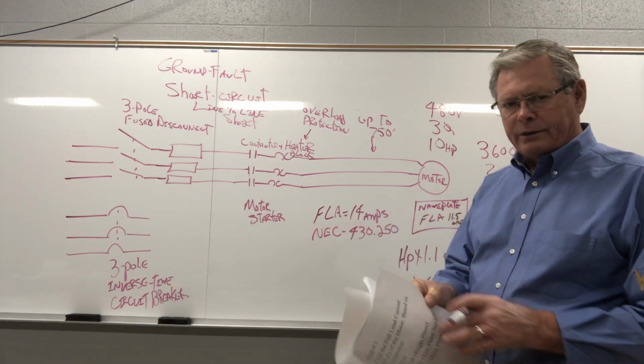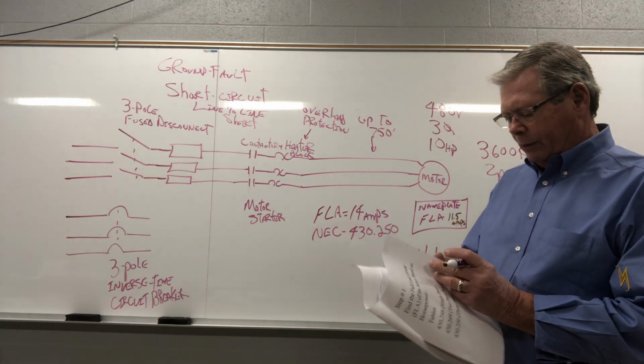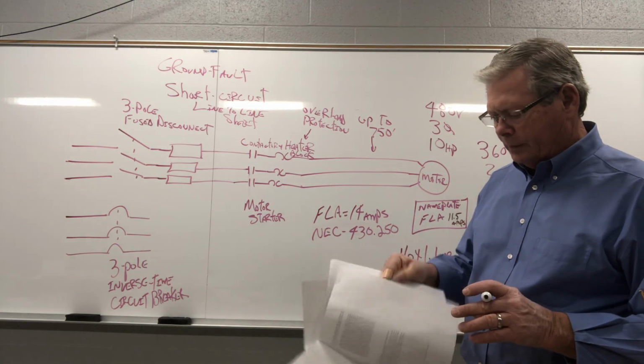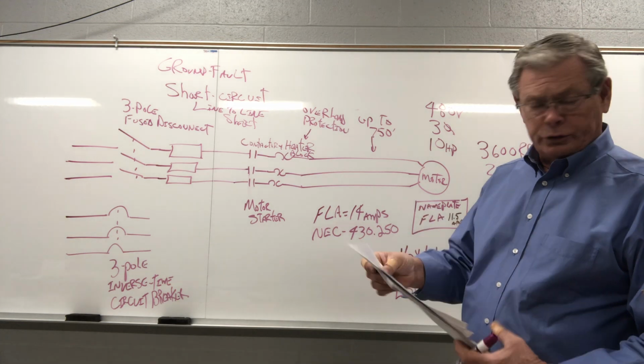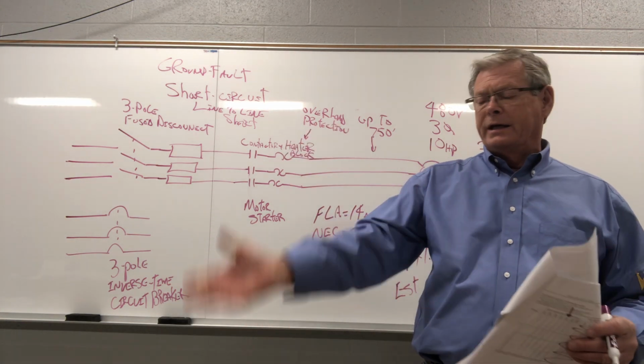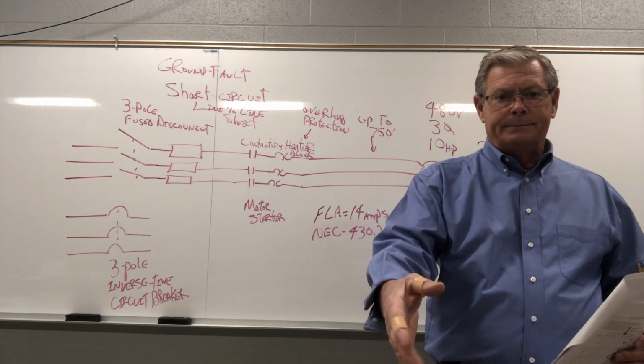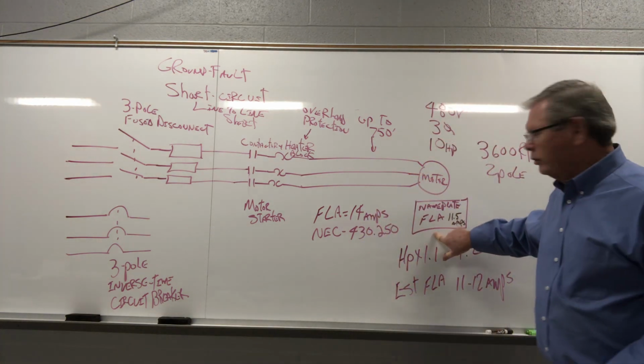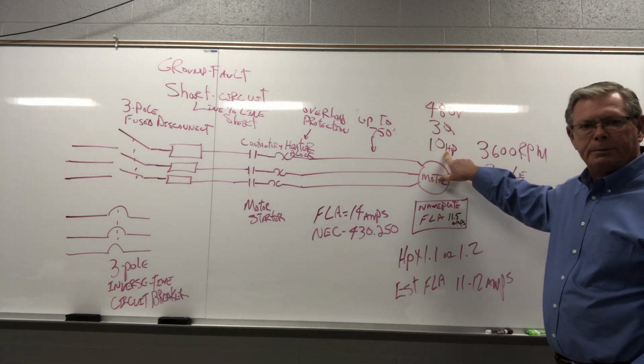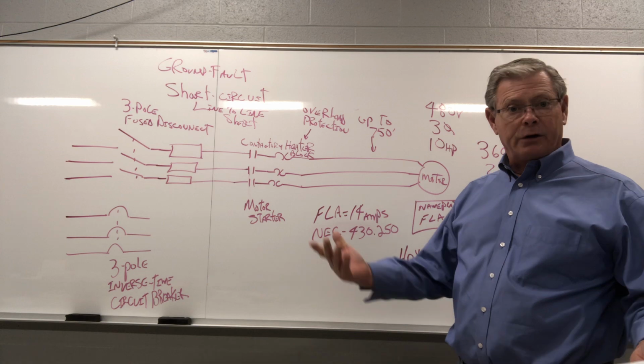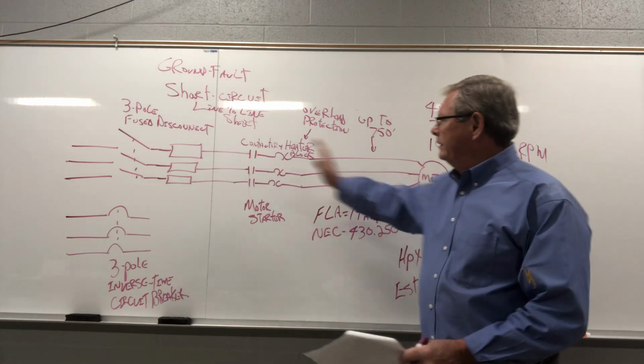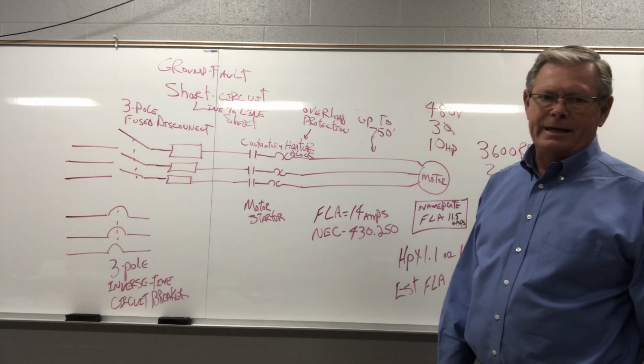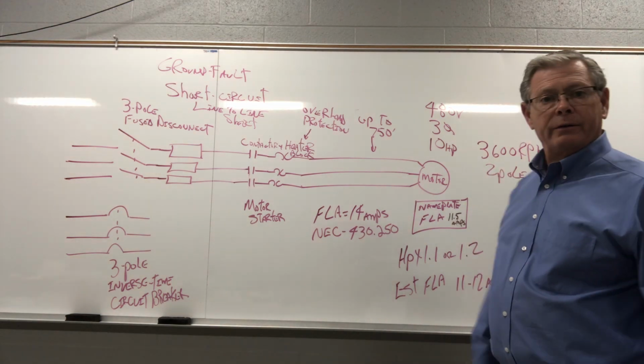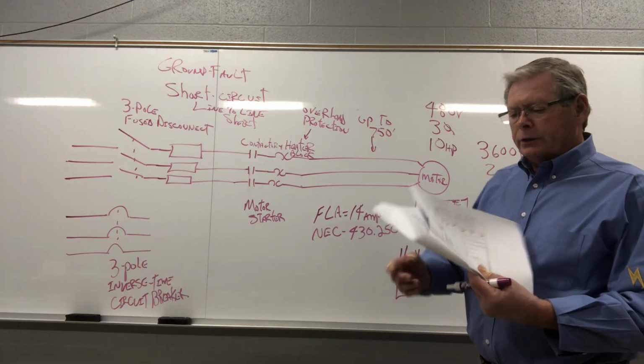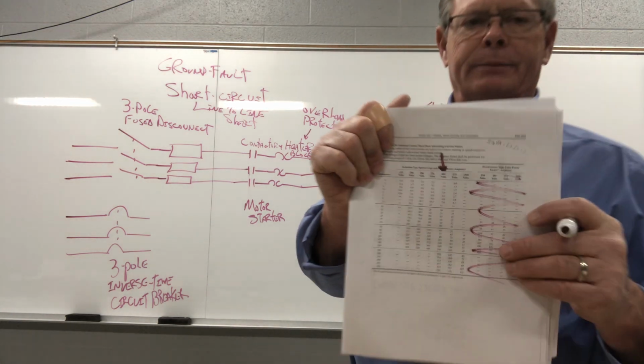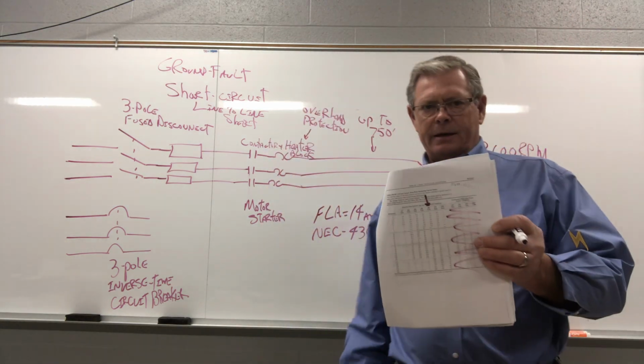All motors are not created equally. So if we burn up that 10 horse GE motor, we are going to go to the storeroom, and we got a 10 horse Baldor, or we got a 10 horse US motor, that's what we're putting back. All your motor manufacturers will have a little different FLA for a 10 horse motor. That's just the way they make them. They have different engineers, they're going to be a little different. So when we build this circuit here, we've got to build it for any 10 horse, 3,600 RPM motor that we put on there, okay? So we're going to table, the first step is to go to this table, 430.250, okay? It's in your handout.